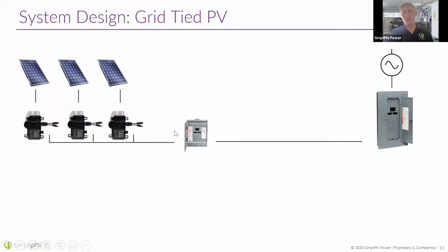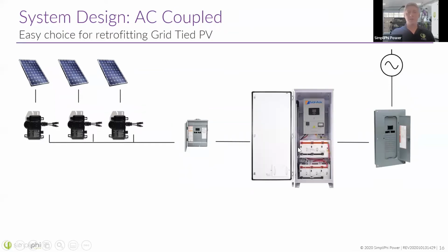So between these two is where you're going to throw your battery-based inverter and batteries. So this is why AC coupling is popular: all your equipment is already outside and you can simply toss in an outdoor rated cabinet like our access unit and then have all that equipment outside. It's an easier installation in general.